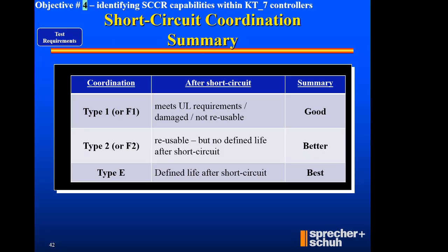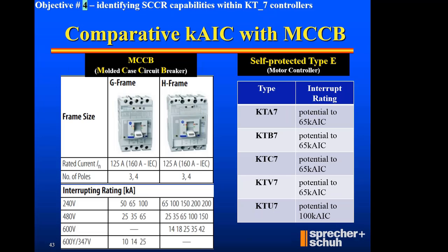And then type E comes along and says, hey, all that's good, but there is a life test after short circuit. So there is a defined life test after short circuit, in that if I were to rate the selection of components, I'd say a type 1 is good, a type 2 is better, but a type E is best because you're going to have a defined life after the short circuit. And so as I sum this up, I was trying to stress the advantages of self-protected type E, potential up to 65 KAIC.